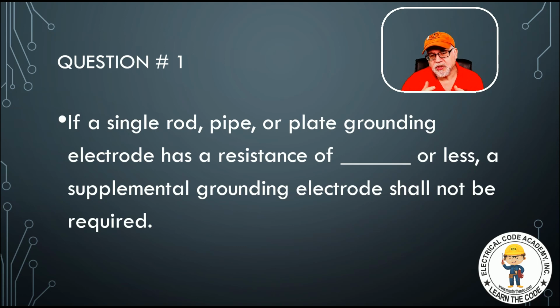Now, an interesting thing to understand about grounding electrodes is that the National Electrical Code gives us 8 types of electrodes. So we have 250.52(A)(1) through (A)(8), and each one of them is unique. The most unique is probably (A)(8), which talks about things like underground metal tanks that might already be present on the premises. But everything has a logical flow. For example, (A)(1) deals with water pipe grounds. Interestingly, water pipe is not always metal; it's plastic or PVC, not always metal. But if you do have a metal water pipe in the ground in contact with the earth for 10 feet or more, then it can qualify as an electrode.